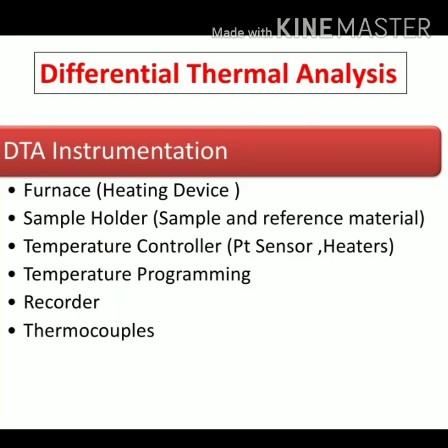Next we will see the instrumentation of DTA. As already seen, in DTA there is the reference material and the sample material in a furnace. The main components of the instrument are the furnace, sample holder, temperature controller, temperature programmer, recorder, and thermocouples.